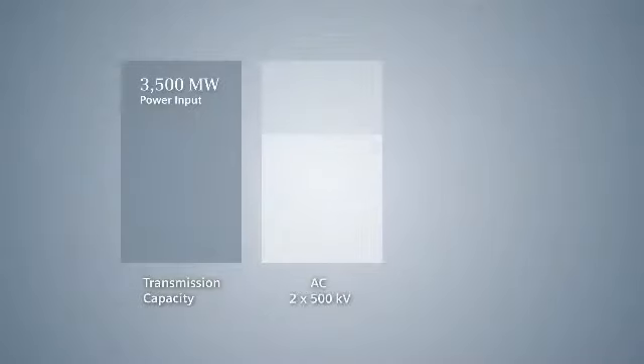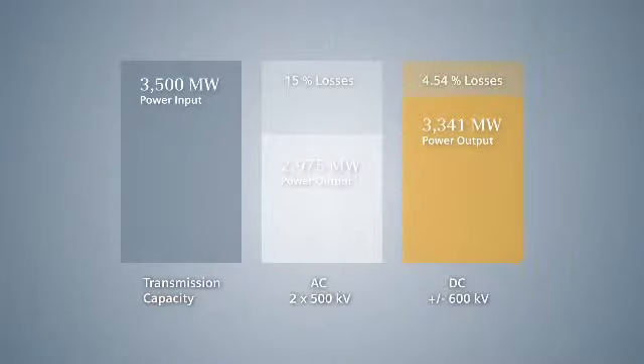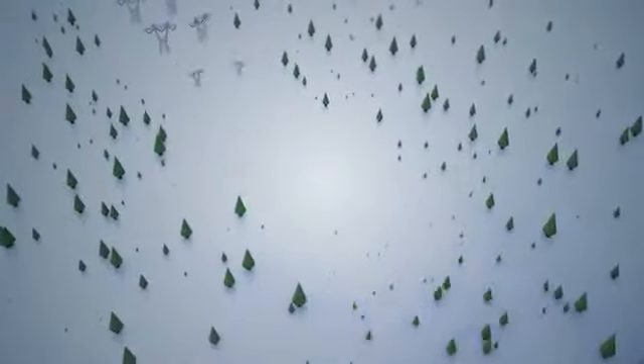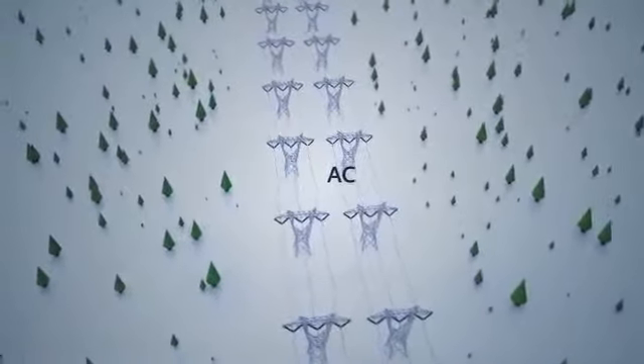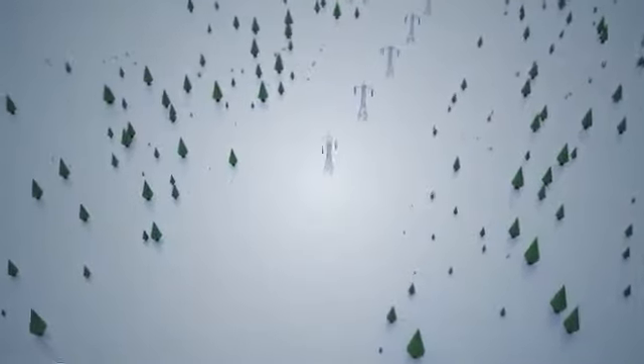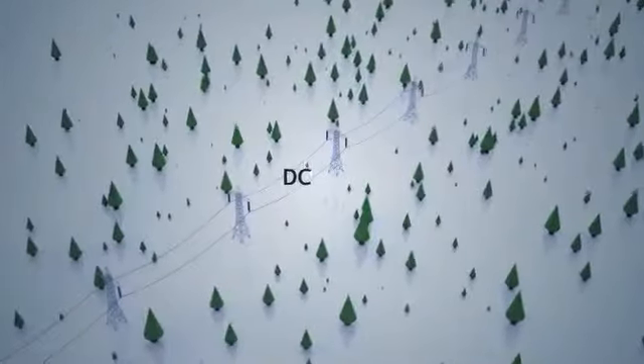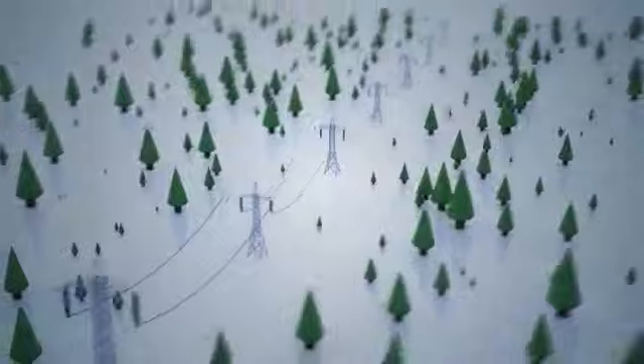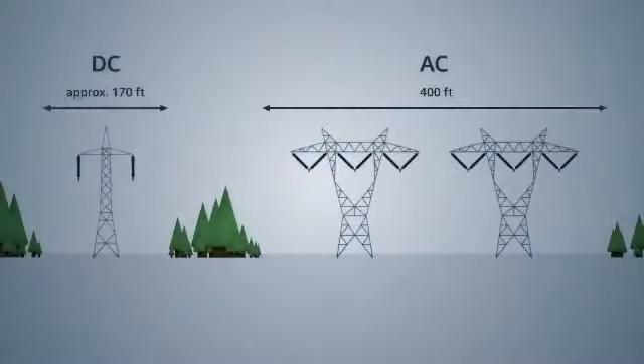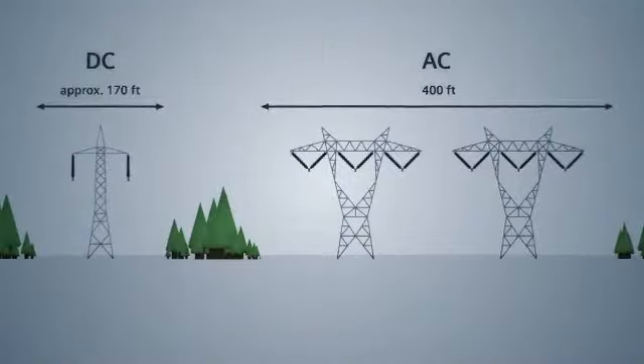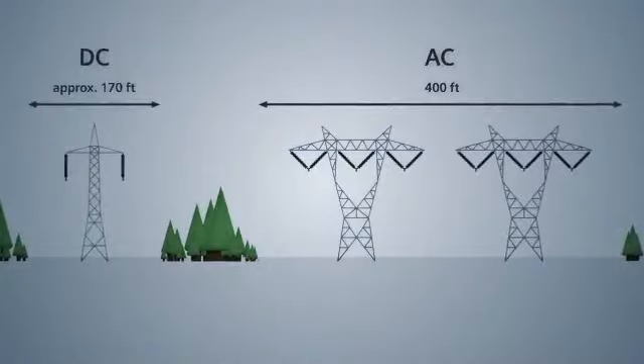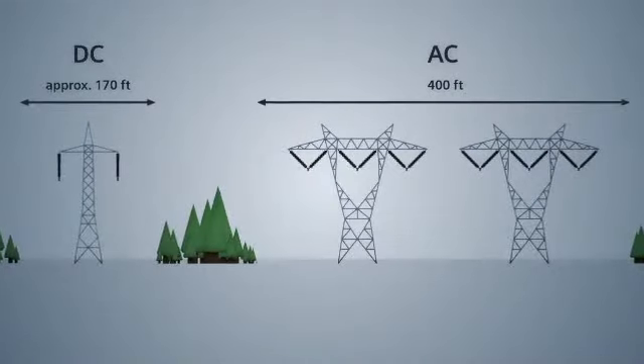At a transmission capacity of 3,500 megawatts, AC transmission lines can have losses of up to 15% over a distance of 600 miles. Compared to this, DC line losses amount to only 4.5%. Typically, large-scale AC needs 2 parallel redundant systems with 3 conductors each. DC needs only 1 bipolar system with 2 conductors. This means DC systems require considerably less space than conventional AC transmission systems. They allow for a significant reduction of the overall environmental impact associated with overhead line construction and help to substantially reduce right-of-way costs.